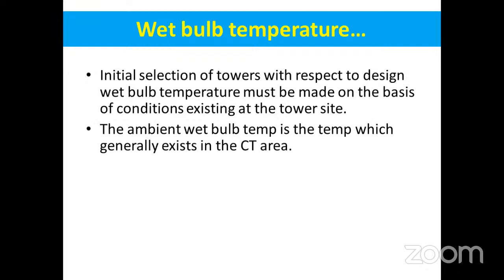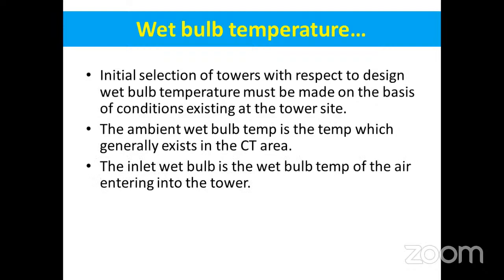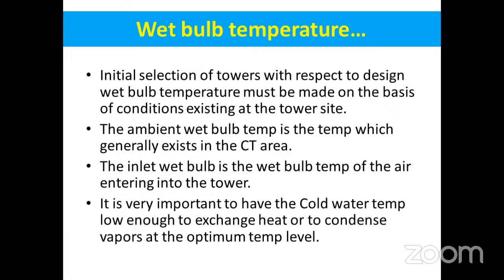The ambient wet bulb temperature is the temperature which generally exists in the cooling tower area, whereas the inlet wet bulb temperature is the temperature of the air entering into the tower. The air entering into the tower is not the air in the surrounding area, sir. It is coming from area other than the cooling tower. It is being drawn in by the low pressure created inside the tower. It is very important to have the cold water temperature low enough to exchange the heat or to condense vapors at the optimum temperature level. If the cooling water temperature is low, everything will be fine.